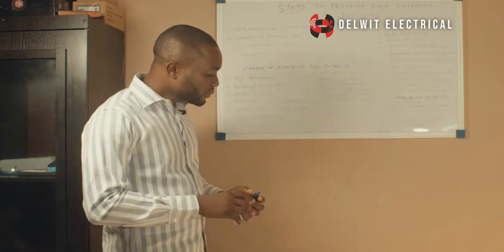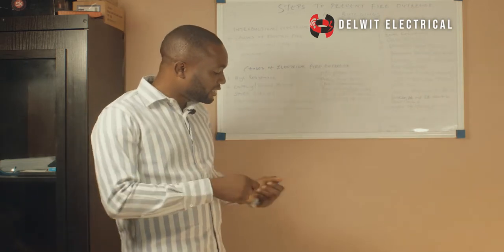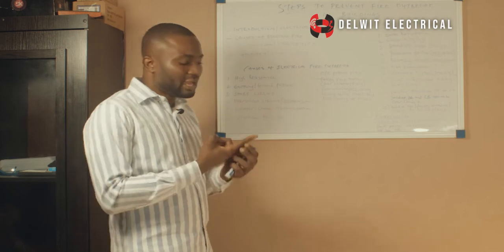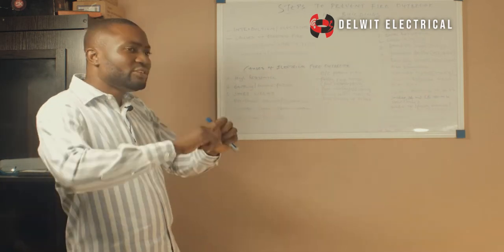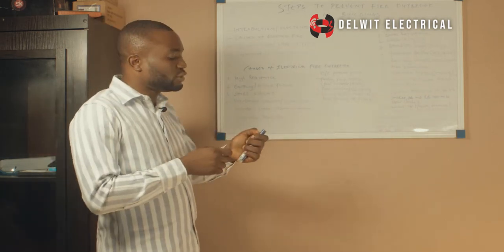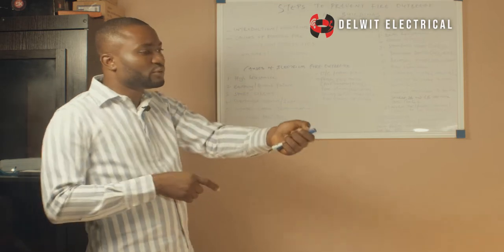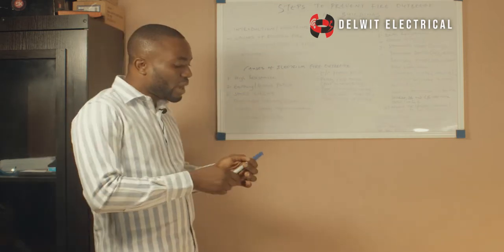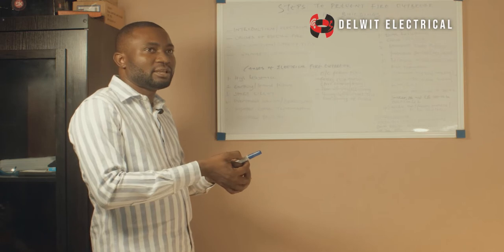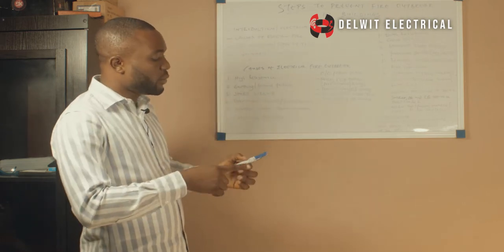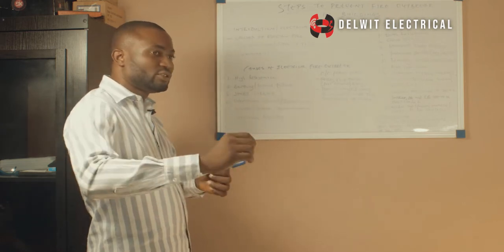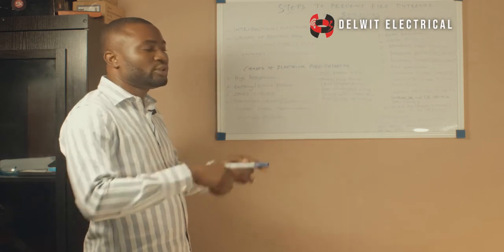Now, I see a lot of people connecting their wires to their 13 amp socket, and you will see strands of copper exposed. When you are using a stripper, you already know the length that is supposed to enter the port of the live, the port of the neutral, and the port of the earthing. So why strip excess? Those excess strands you are stripping, a time will come where the live will have excess, the neutral will have excess, and they will join along the line.